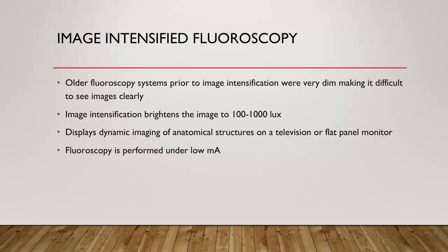Now, why is the image so dim in fluoroscopy without image intensification? Fluoroscopy is performed under low mA settings. Your mA settings control image intensity or brightness. That's why the image appears dim.